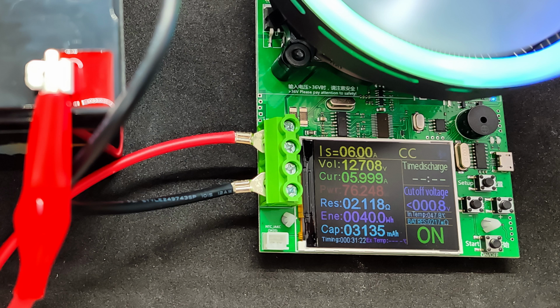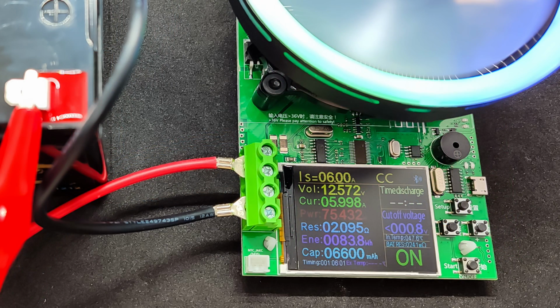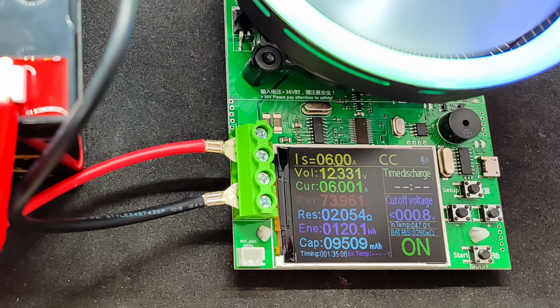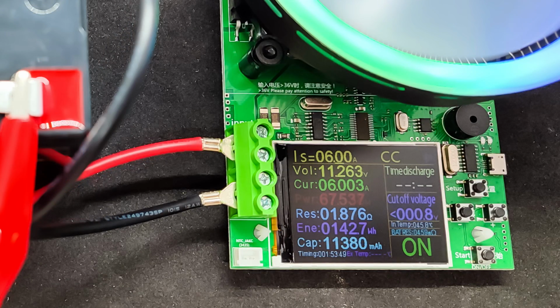Considering its voltage, this is just over 3 amp hours, which is a quarter of the declared capacity. 1 hour after the start of the test, almost 84 watt-hours of energy, or 6.6 amp hours, have been delivered, more than half of the declared capacity. Another half hour later, the voltage dropped to 12.3 volts, delivered 120 watt-hours of energy, which corresponds to 9.5 amp hours. The test is nearing completion.